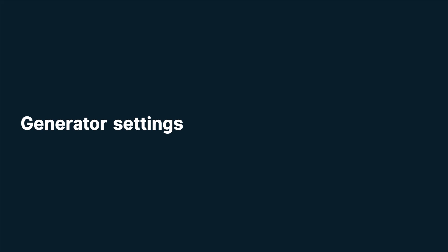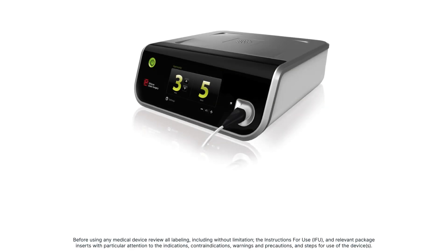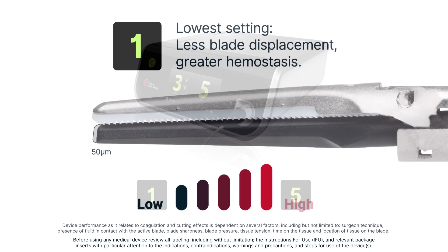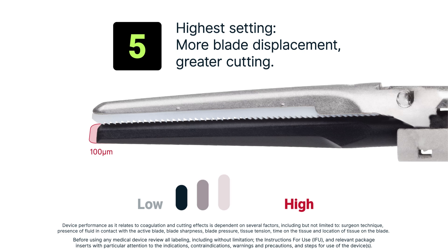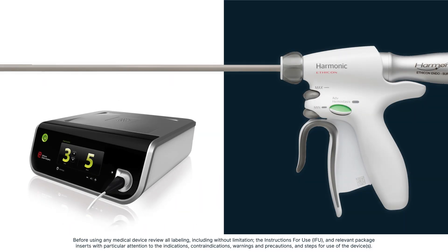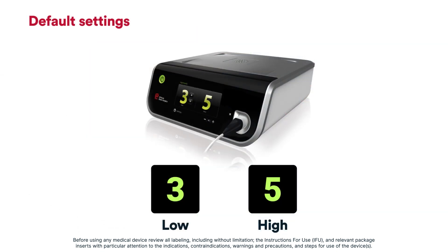Generator settings. Generator output is controlled by the power setting and ranges from 1 as the lowest energy output to 5 at the highest. At power setting 1, the blade will displace approximately 50 micrometers, resulting in greater hemostasis. Power setting 5 causes the blade to displace in the range of 100 micrometers, resulting in a greater cutting effect. Most generators have min and max buttons for easy use, with default settings of min at 3 and max at 5.